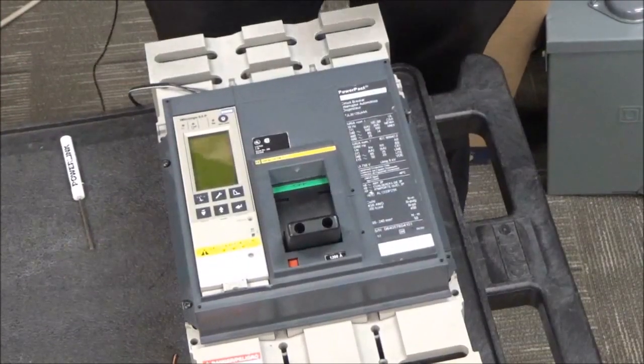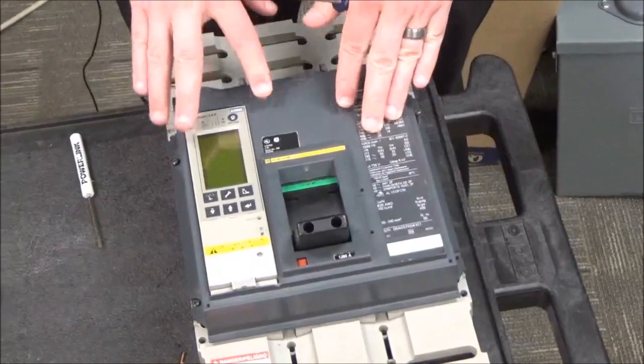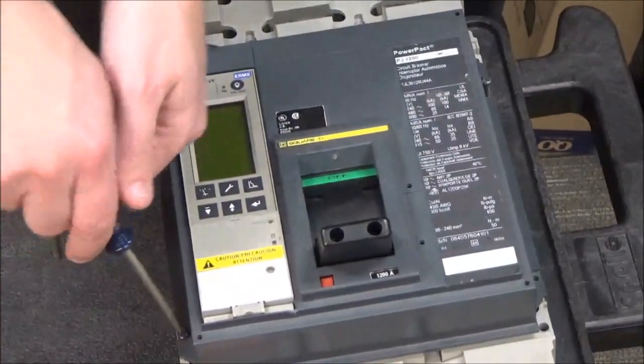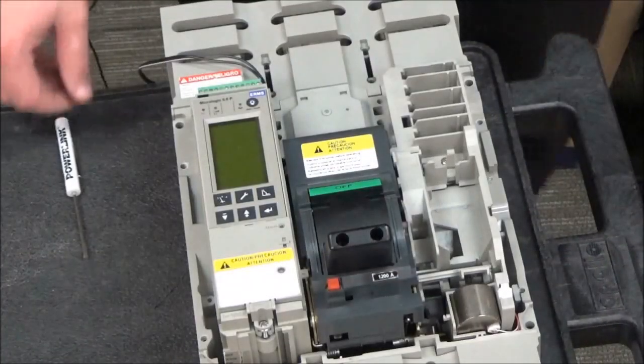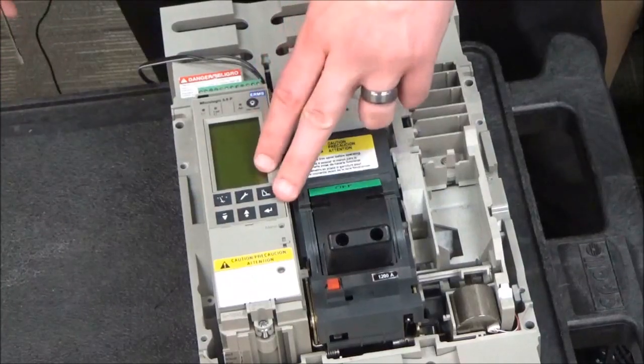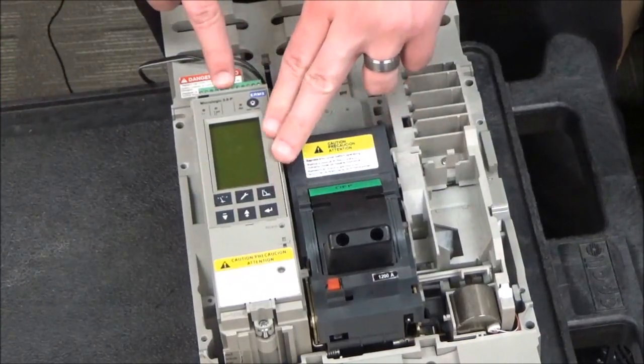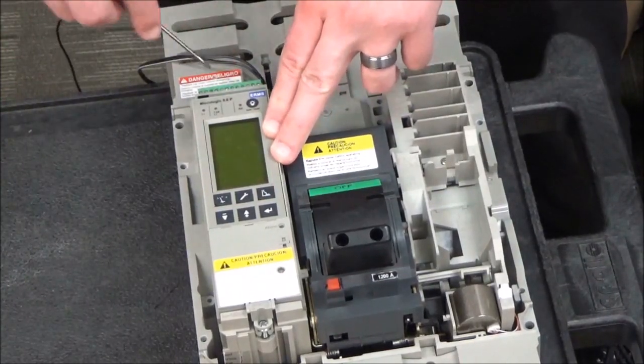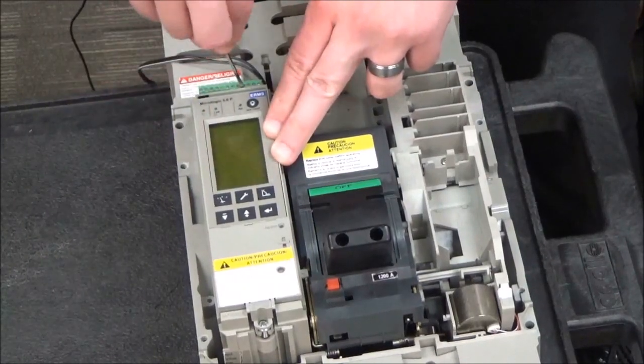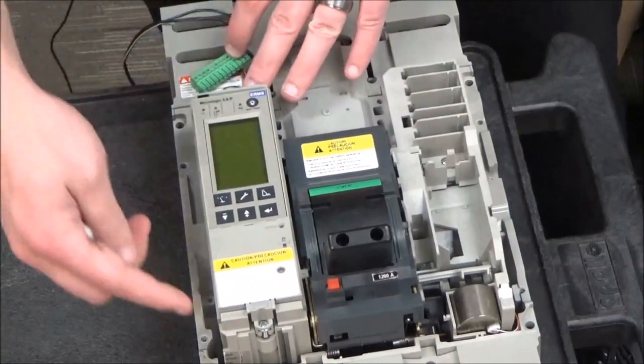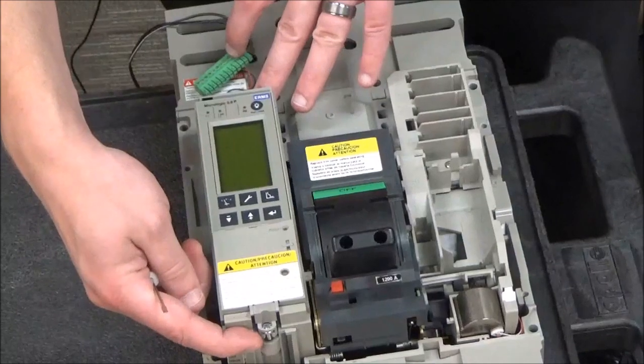You'll start by removing the accessory cover on the breaker. Then you'll remove the trip unit by taking out the green Phoenix connector and loosening these two captive screws.